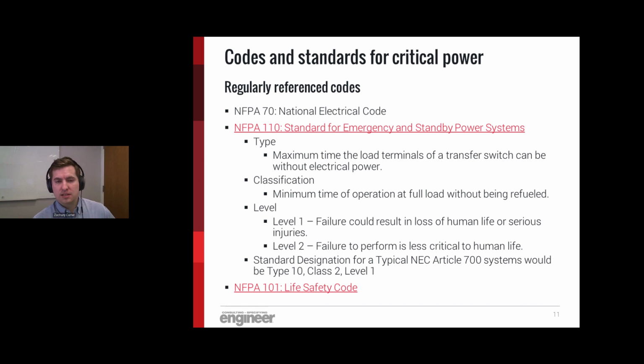NFPA 110 is the standard for emergency and standby power systems. This relates to installation, testing, and maintenance of emergency generators. With this, the three things that are most important in NFPA 110 for your mission critical facilities are the type, the classification, and then the level.